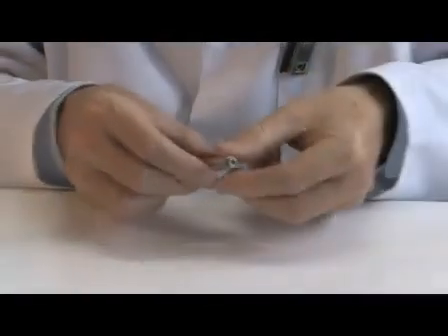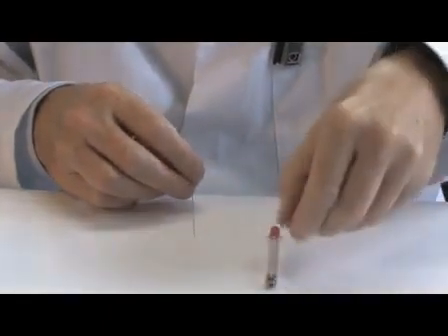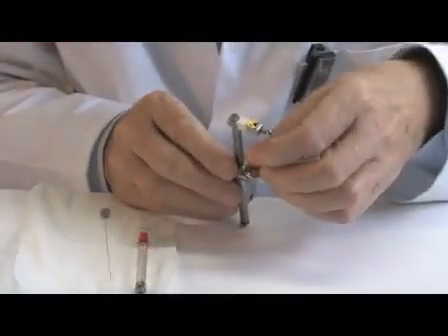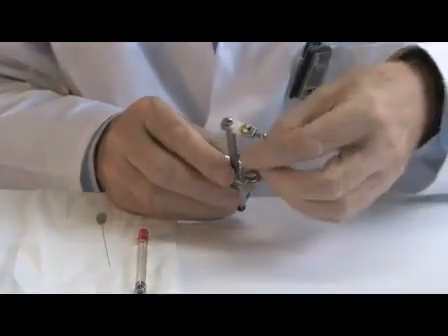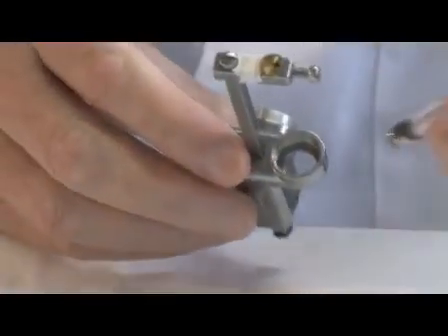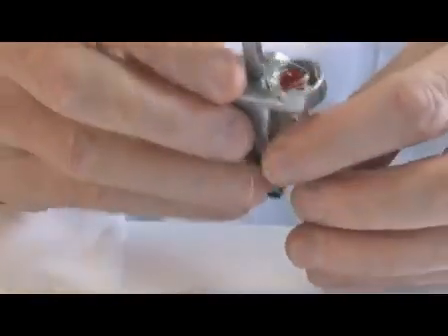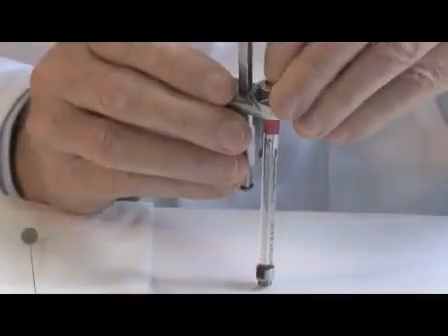Remove the needle and the plunger from the syringe. Leave the Teflon ferrule in place. Remove the retaining nut from the dispenser with the aid of a small coin. With the ratchet arm fully withdrawn, insert the syringe without its plunger and needle through the holding ring of the dispenser. Replace the retaining nut, gasket side facing the syringe, and screw it in tightly on the open end of the syringe.